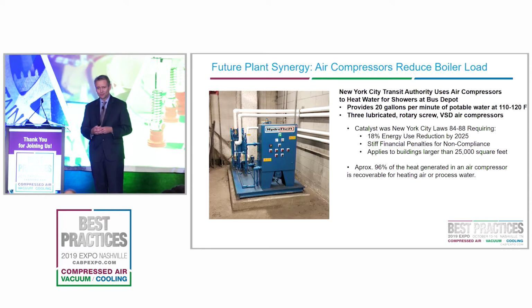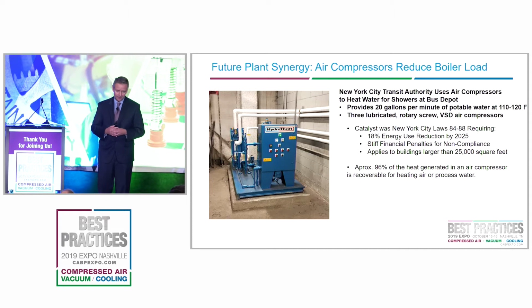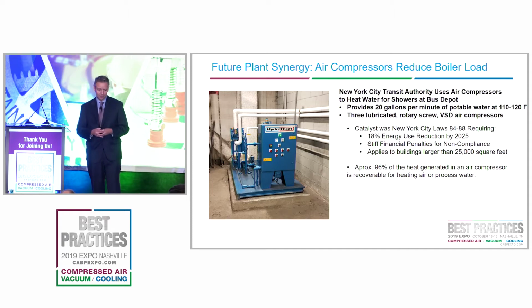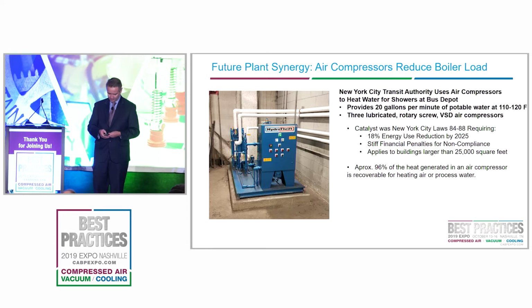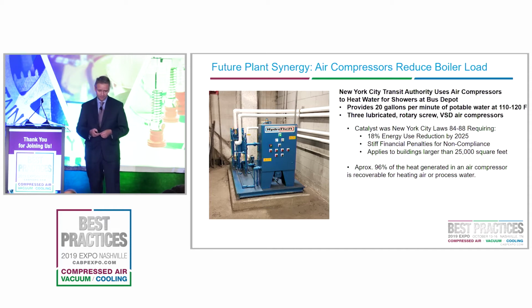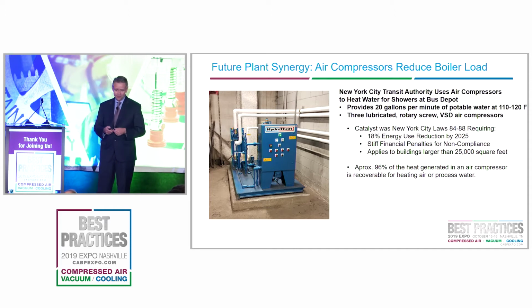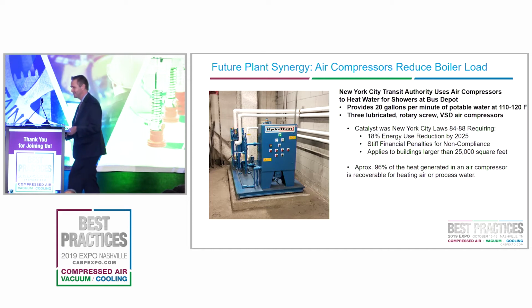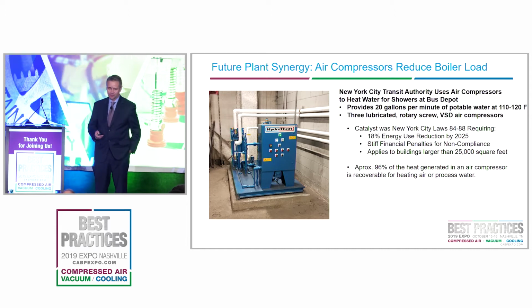Here's a story we wrote about the New York City Transit Authority. They use their air compressors now to heat water for the showers at the bus depot, and it completely takes care of it. Three normal lubricated rotary screw VSD air compressors are providing 20 gallons per minute of potable water at 110, 120 degrees F. It required an engineering firm that works with both systems to get involved.